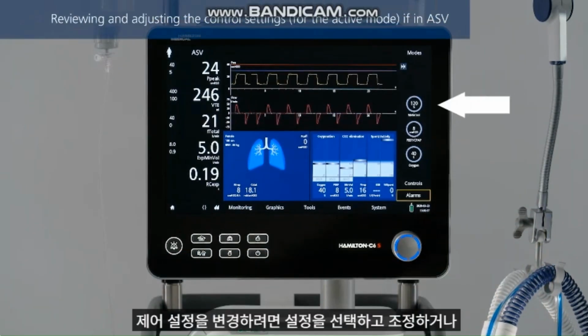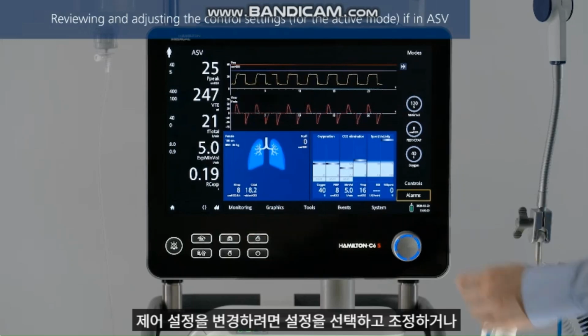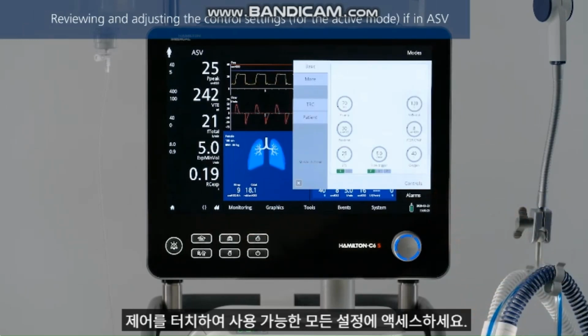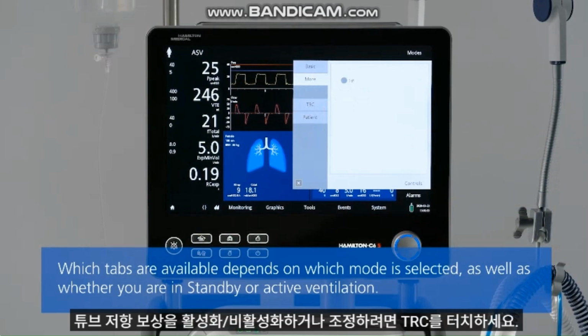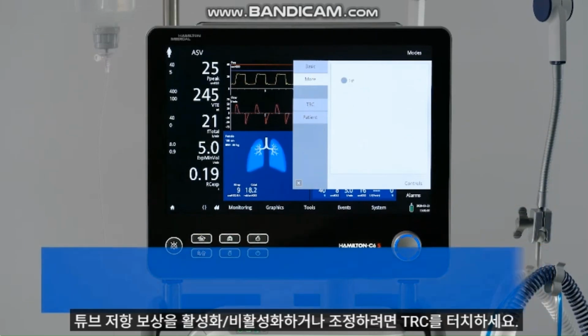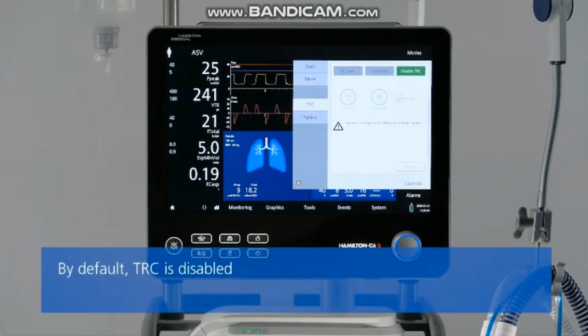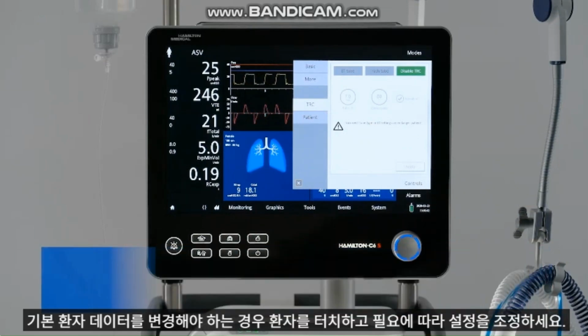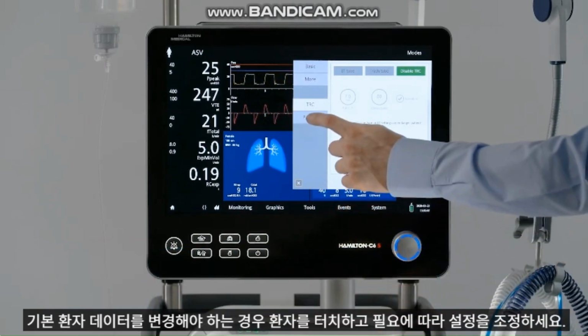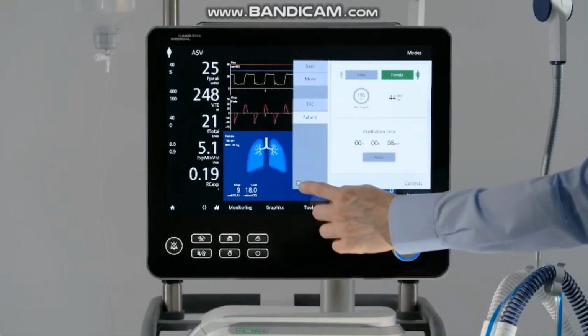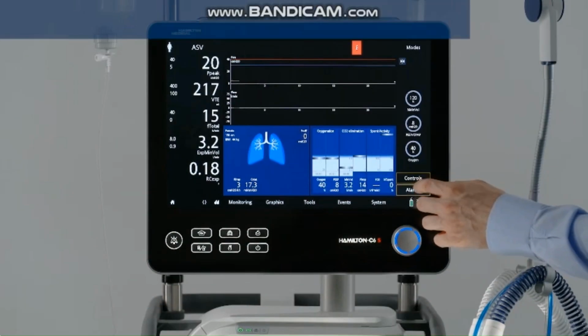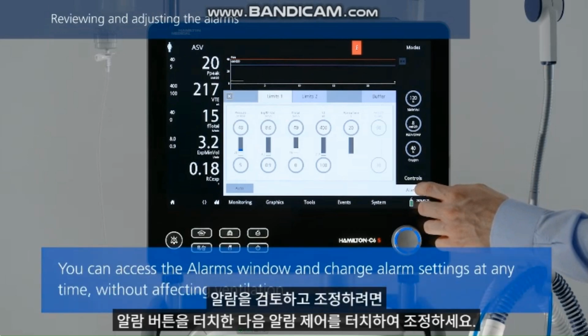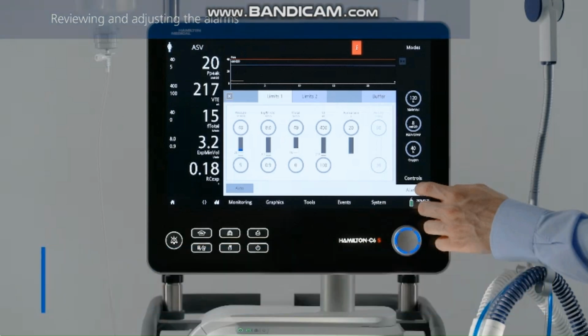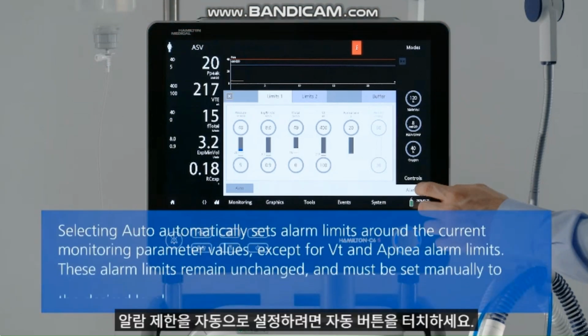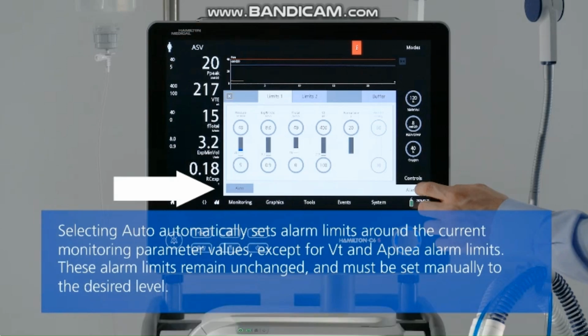To change any control settings, select and adjust the setting or touch Controls to access all the available settings. To enable, disable, or adjust tube resistance compensation, touch TRC. If you need to change basic patient data, touch Patient and adjust the settings as needed. To review and adjust the alarms, touch the Alarms button. Then touch the alarm control and adjust it. To set alarm limits automatically, touch the Auto button.